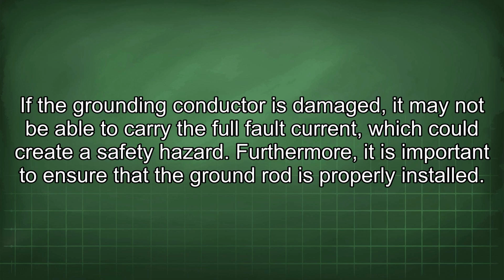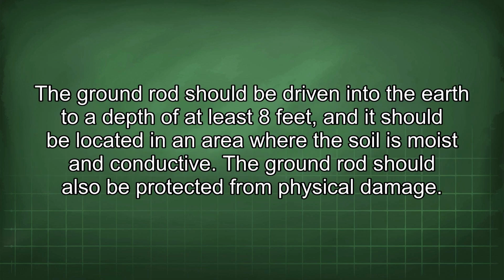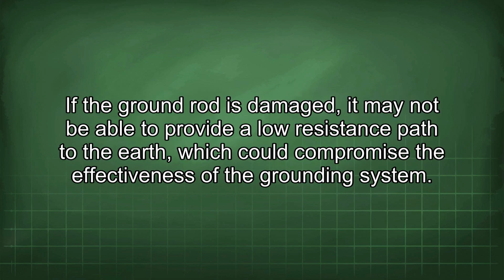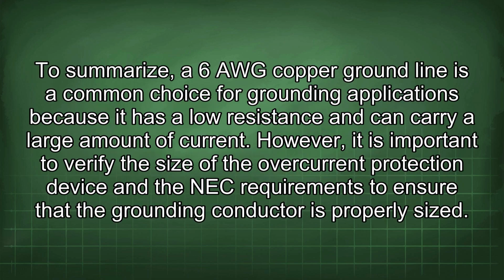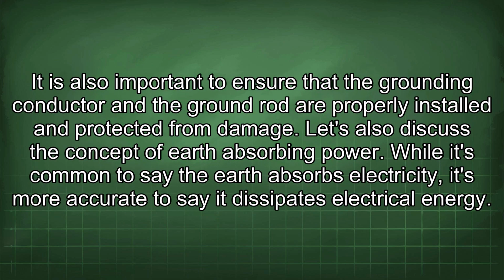a safety hazard. Furthermore, it is important to ensure that the ground rod is properly installed. The ground rod should be driven into the earth to a depth of at least 8 feet, and it should be located in an area where the soil is moist and conductive. The ground rod should also be protected from physical damage. If the ground rod is damaged, it may not be able to provide a low resistance path to the earth, which could compromise the effectiveness of the grounding system. To summarize, a 6 AWG copper ground line is a common choice for grounding applications because it has a low resistance and can carry a large amount of current. However, it is important to verify the size of the overcurrent protection device and the NEC requirements to ensure that the grounding conductor is properly sized.